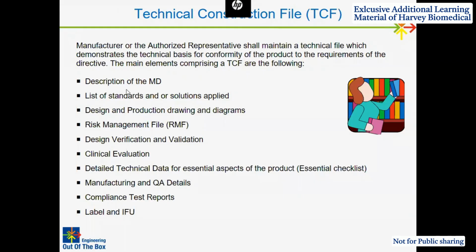It means device description, description of the medical device, list of the standards and solutions applied, design and production drawing diagrams, and the risk management file. The risk management file means a risk management plan, risk management report, hazard analysis, usability report, and post-market surveillance with respect to risk, which we also have to fulfill. Design verification and validation means design input, output, transfer and changes, verification, validation. Everything will be covered in the design verification and validation.